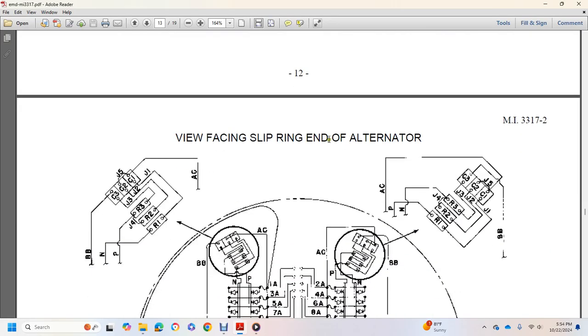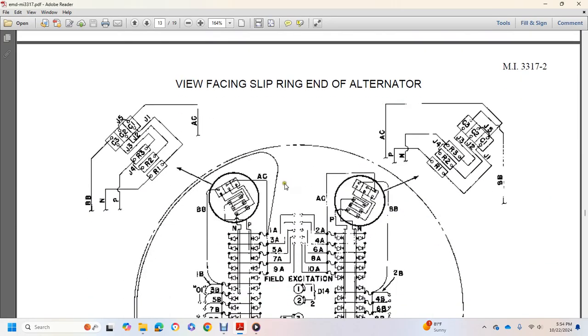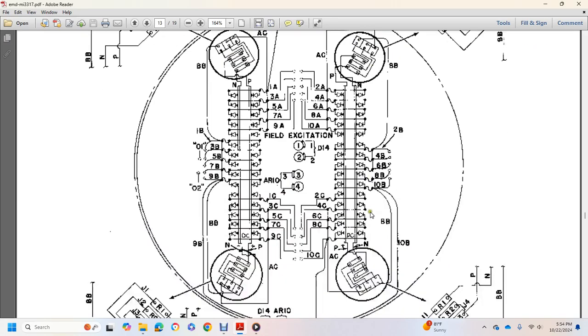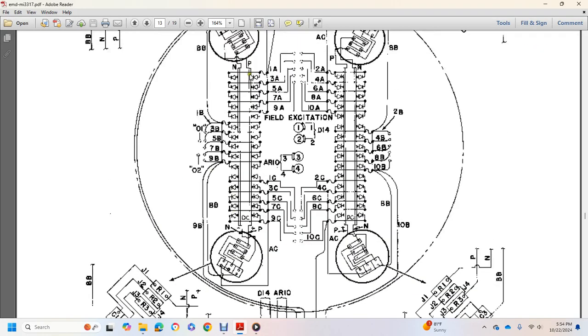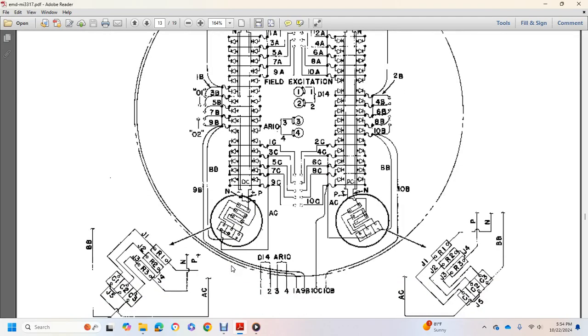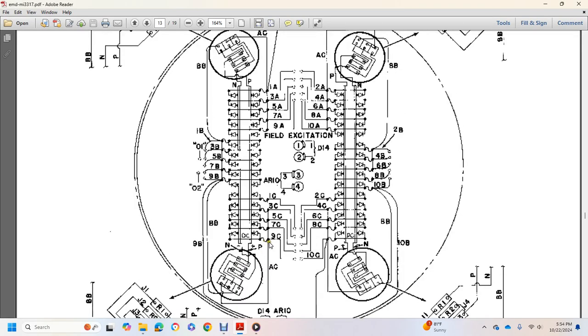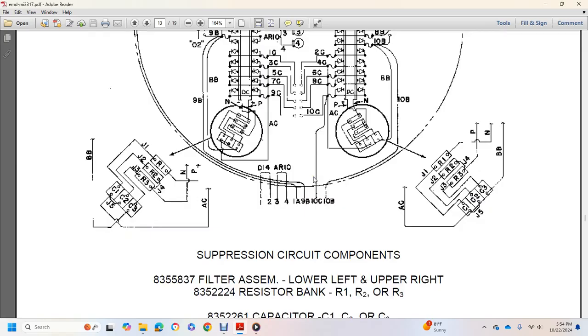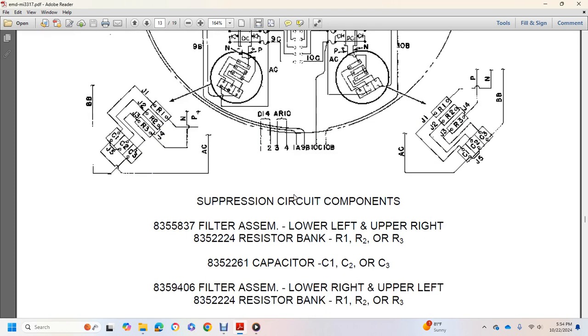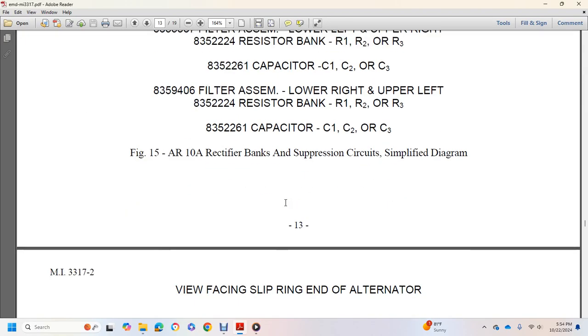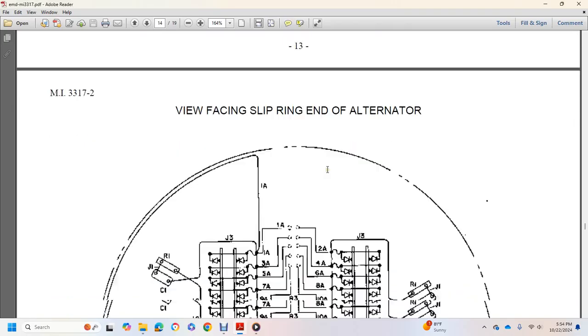Alright, the view facing the slip ring end of the alternator. This shows a good drawing of the brush holder and slip rings, and I'm going to actually print this. It shows the buses, field extensions, brush holders, and field excitation for the suppression circuit component. Filter assembly, lower left, upper right: resistor banks R1, R2 and 3, capacitors 1, 2, and 3. Filter assembly, lower right, upper left: resistor bank R1, 2, and 3, capacitors 1, 2, and 3.